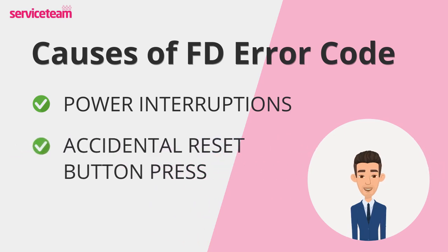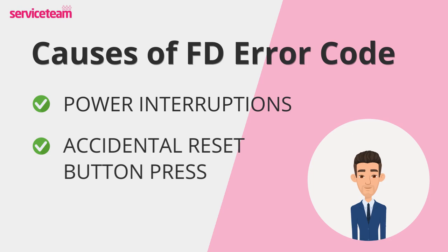Next up, an accidental press of the reset button. This often happens during maintenance or even while cleaning around the boiler. It's a simple mistake but enough to trigger the FD code.